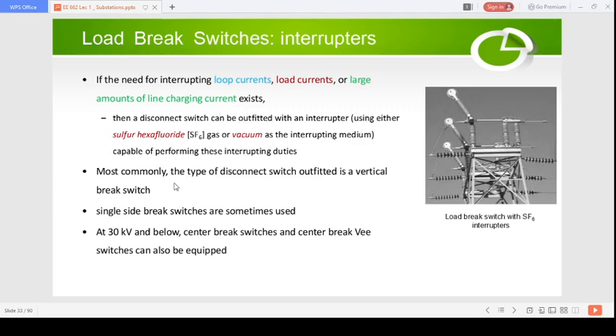Most commonly, the type of disconnect switch outfitted is a vertical break switch. Typically the vertical break switches are outfitted with what you call the interrupters. Single side break switches are sometimes used. Mostly they use the single side break switches equipped with SF6 or vacuum interrupting medium in order to facilitate the high current breaking. At 30 kV and below, center break switches or center break V switches can also be used, but at low voltages like 30 kV or below.